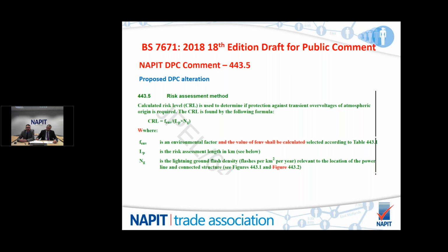So the next one is a DPC comment we have for regulation 443.5, and this is round about the risk assessment. And as you can see from the items on the screen, it's looking at calculate risk level to determine the transient overvoltage of atmospheric origin, and it gives you a formula. It gives you an environmental factor, which is selected from a table 443.1. It's got a risk assessment length in kilometres. It's got lightning ground flash density in flashes per kilometre square per year, relevant to the location of power line and connected structure, and it gives the two figures to which this refers. So we've got figure 443.1 and 443.2, which are going to be shown over in the next slide.